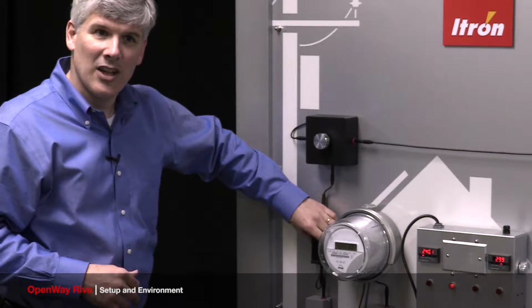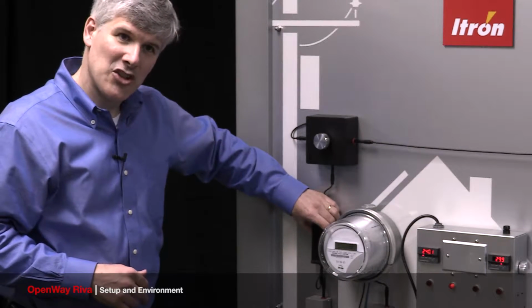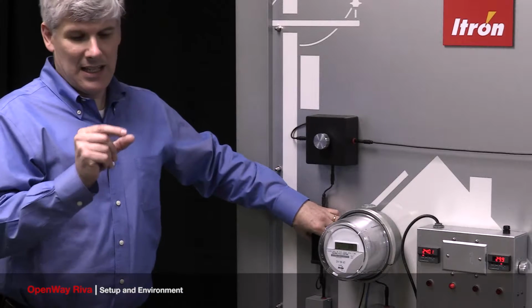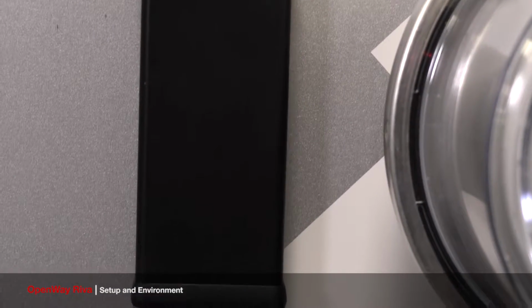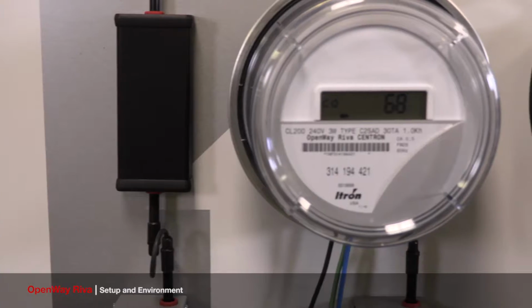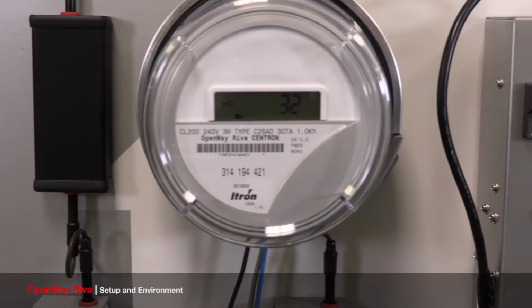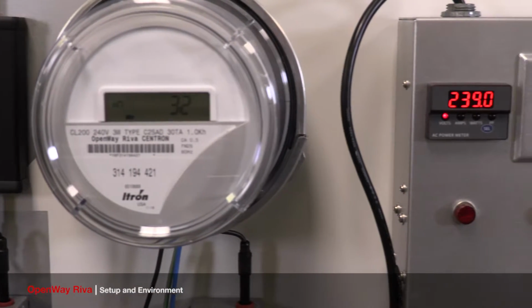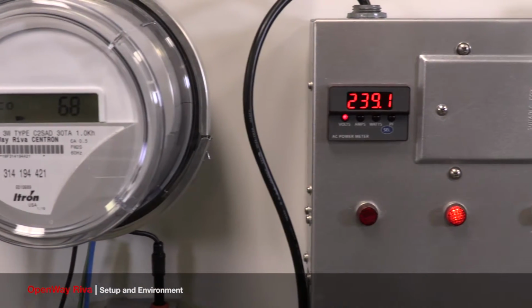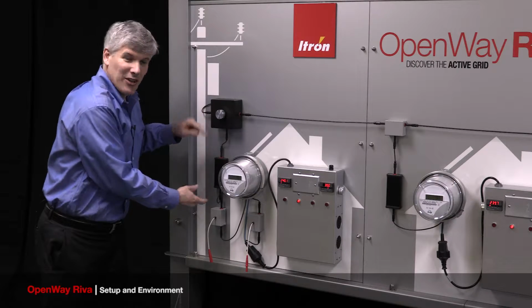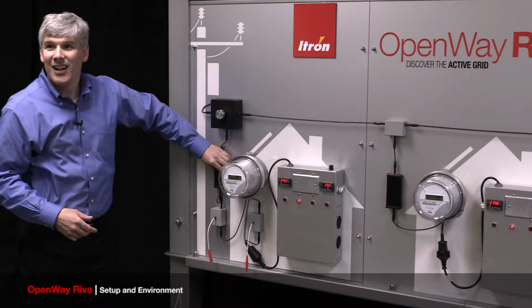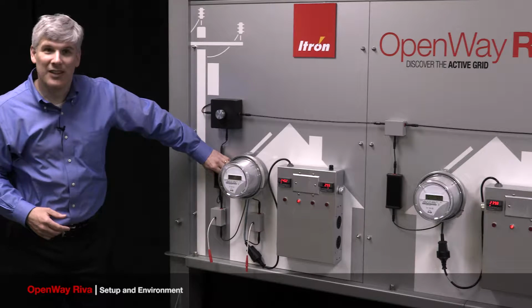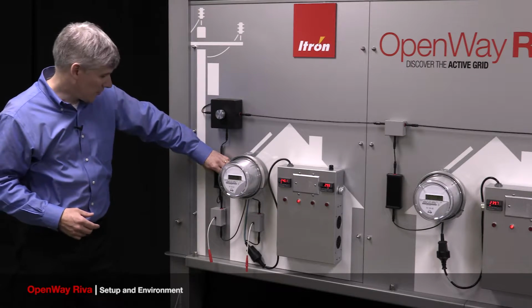What is that? Well, most of these applications work on detecting the small voltage changes that occur when we pull currents into a meter. Of course, a real distribution line, even in the low voltage, the service drop is quite long, and so these are very tiny lines, so we have very little resistance here. So all these black boxes are small resistors to simulate the resistance that's in that service drop.